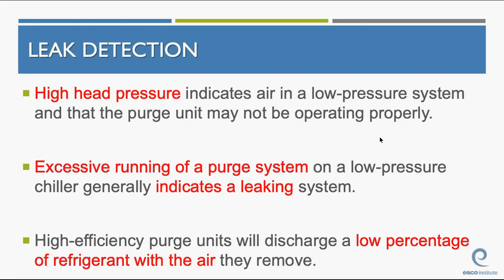High head pressure indicates an air leak in a low-pressure system and that the purge unit may not be operating properly. Again, high head pressure, which is my high side pressure, tells me that there's non-condensables in the system. I either have a leak that's too big for the purge unit to handle, or the purge unit isn't operating properly. Excessive running of a purge system on a low-pressure chiller generally indicates a leaking system. High-efficiency purge units will discharge a low percentage of refrigerant with the air they remove. Folks, this is important. That's why it's in red. High-efficiency purge units will discharge a very low percentage of refrigerant in the air that they remove. Okay, purge units.